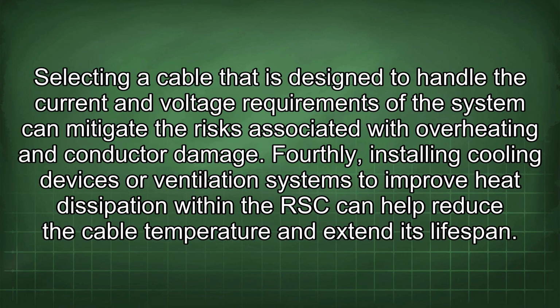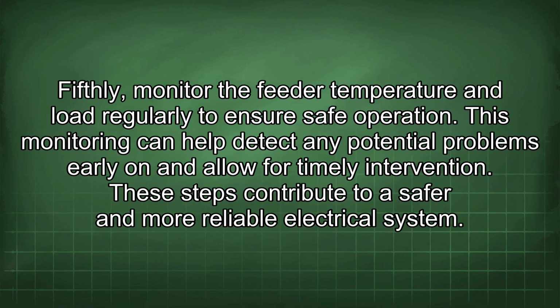Selecting a cable that is designed to handle the current and voltage requirements of the system can mitigate the risks associated with overheating and conductor damage. Fourthly, installing cooling devices or ventilation systems to improve heat dissipation within the RSC can help reduce the cable temperature and extend its lifespan. Fifthly, monitor the feeder temperature and load regularly to ensure safe operation. This monitoring can help detect any potential problems early on and allow for timely intervention. These steps contribute to a safer and more reliable electrical system.